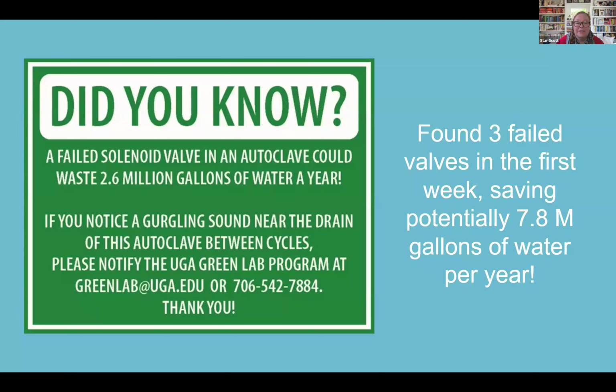So we added these stickers as part of an educational campaign to teach our users how to listen for and identify failed solenoid valves. While they're waiting in front of the autoclave for that cycle to finish, they see this sticker, and it says a failed solenoid valve in an autoclave can waste 2.6 million gallons of water a year. So if you hear gurgling at the drain when this unit isn't cycling, then give us a call. In the first week that we posted these, we got calls identifying 3 failed valves on campus, potentially wasting upwards of 7.8 million gallons of water per year.